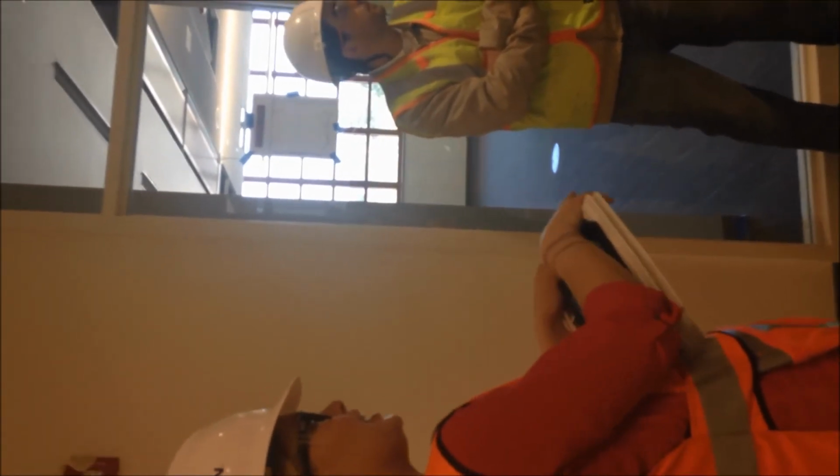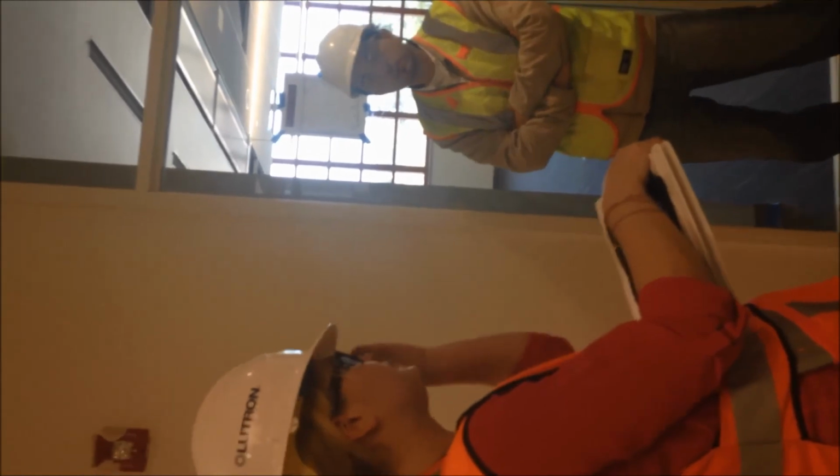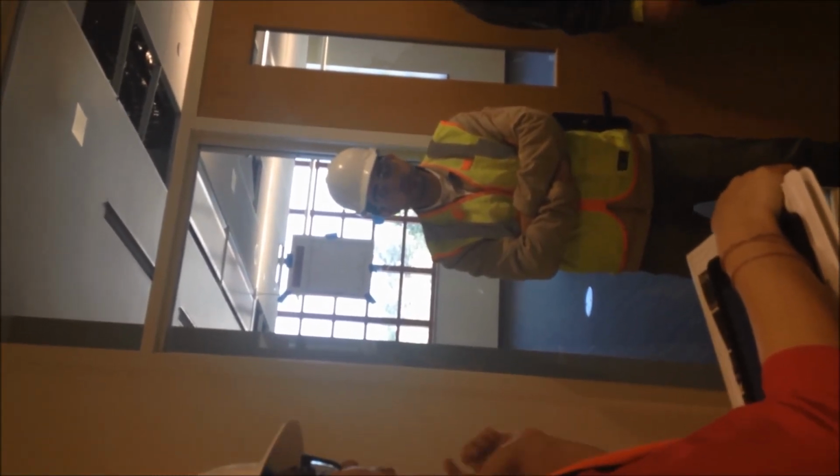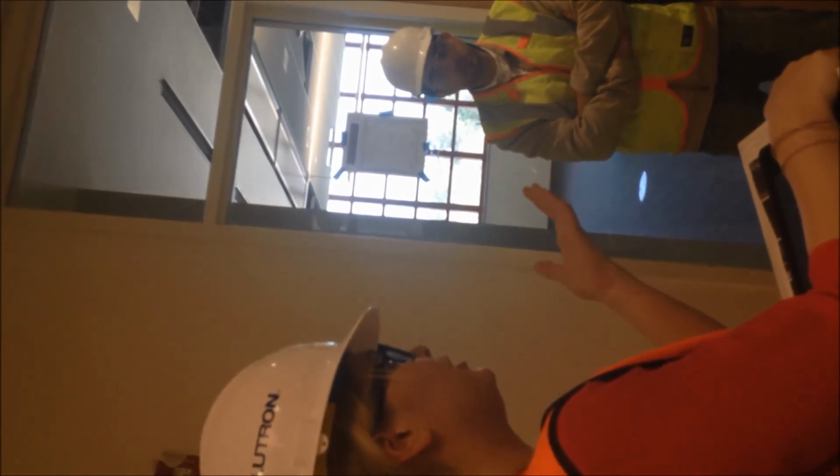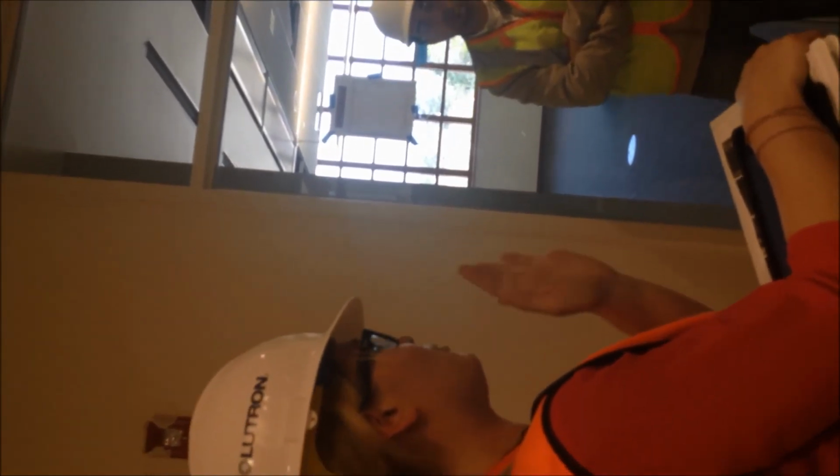The cleaning crews, they want to come in and be able to just walk in and have certain areas light up, or hit a switch. The thing with time clocks is they're like an egg timer. So if we sweep the lights off at 10 and someone comes in at 10:05, they won't turn on. If they come in at 10:15, the lights will turn on. But for 15 minutes, they won't work. All right, they would just need to be aware of that.